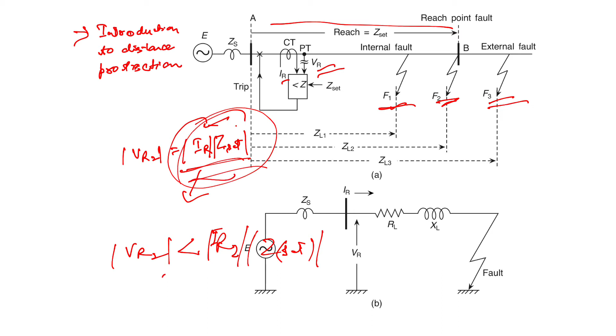Let us suppose that a fault occurs in the system, then the current would increase. When the current increases, the voltage seen by this PT is less and this component is large. It means that VR is less than IR into Z set. Let us suppose that we are taking the 2 arbitrarily. The current is very high in that case, so this drop is high, and this component is much more than whatever is seen by the relay. So in that case it will trip.